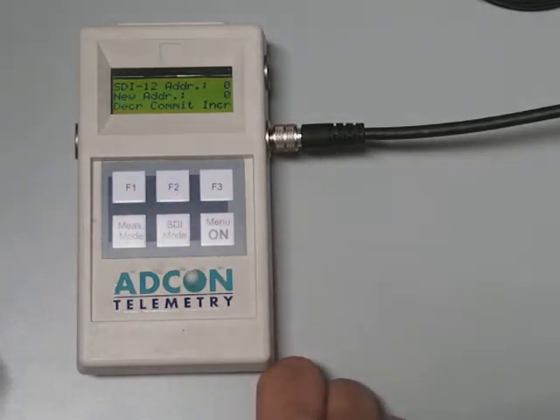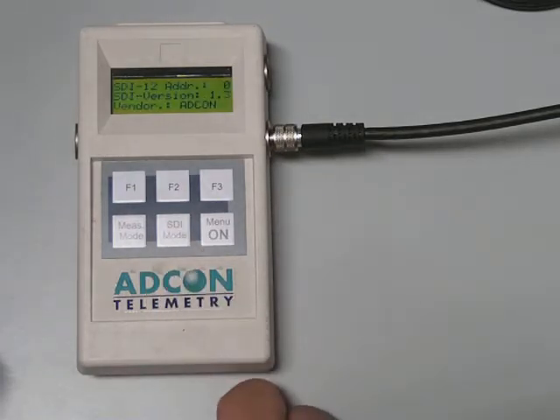Now push the SDI button again, and the A511 will show you in the center line on which SDI12 protocol version your sensor is operating, and in the bottom line it will display the vendor ID. In our case, we are connecting to an SDI12 soil moisture probe from Adcon, running on protocol version 1.3.